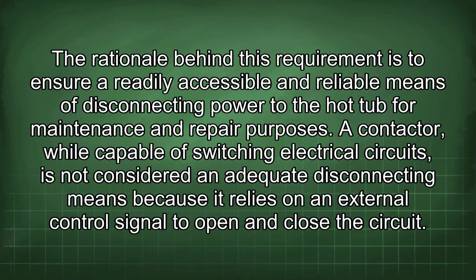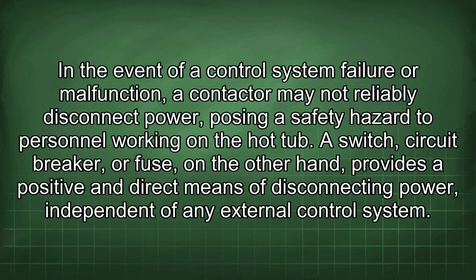A contactor, while capable of switching electrical circuits, is not considered an adequate disconnecting means because it relies on an external control signal to open and close the circuit. In the event of a control system failure or malfunction, a contactor may not reliably disconnect power, posing a safety hazard to personnel working on a hot tub.